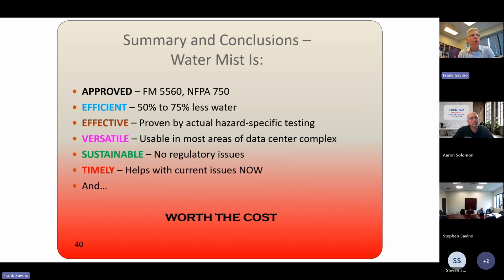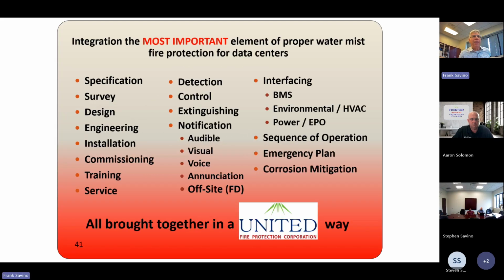Okay, summary and conclusion. So you have Factory Mutual 5560 and NFPA 750 approves water mist. It's very efficient, 50 to 75% less water. It's effective, proven by actual hazard testing. Versatile, you can do just about the whole data center complex. It's sustainable with regard to environmental issues. And really, it's the latest state-of-the-art fire protection for large data centers. Integration is very important: your field surveys, your detection, control, notification, annunciation, interfacing with BMS and HVAC. That's all part of an integrated overall fire protection solution. It's not just water mist, it's other parts of the fire protection solution that go along with it.